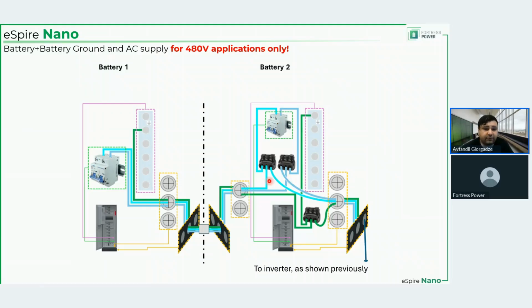So from the inverter, you bring L1 and L2, or L2 and L3, L3 and L1, that doesn't matter. And you deliver that AC supply to this Polaris connector, which then splits it between battery 2 and battery 1. Same with the ground. So ground connects to the Polaris connector of the second battery, of the first battery, and then goes to the inverter ground. And these cables, like these light blue and slightly darker blue cables, these are the ones that you are taking as the AC supply. But again, this is for 480 volts only.